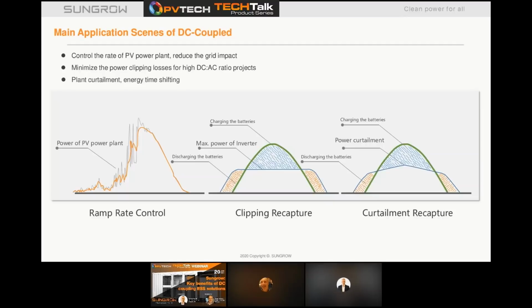Likewise, with the graphic on the right, curtailment recapture would be used when the network operator limits export. In non-storage scenarios, this would mean either the PV plant switching off or turning down, both leading to yield losses. Like clipping recapture, the plant would carry on as normal, however diverting the energy to the batteries rather than reducing its output, again allowing you to export at a later stage when network conditions are better.